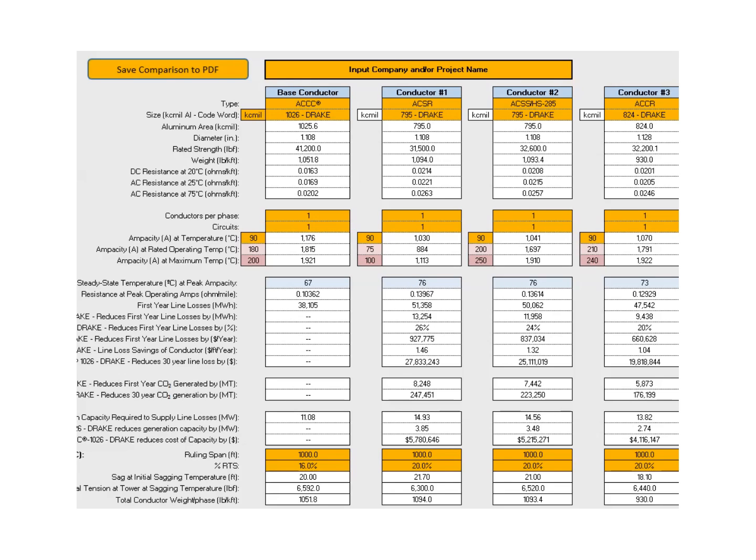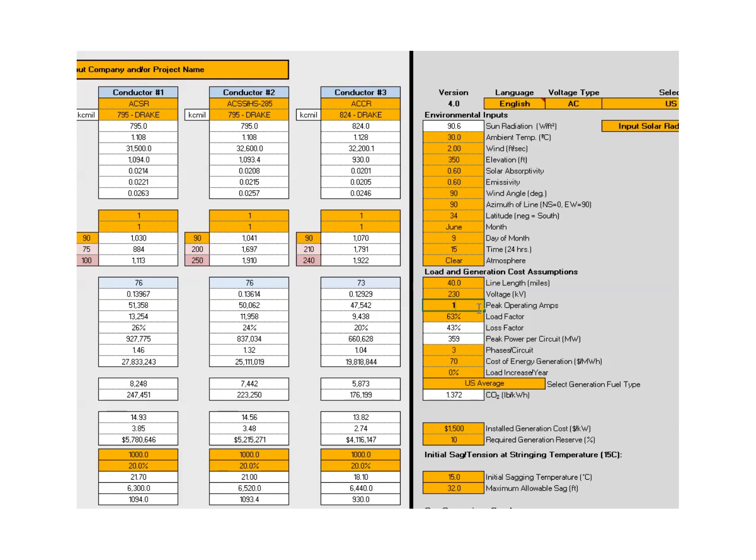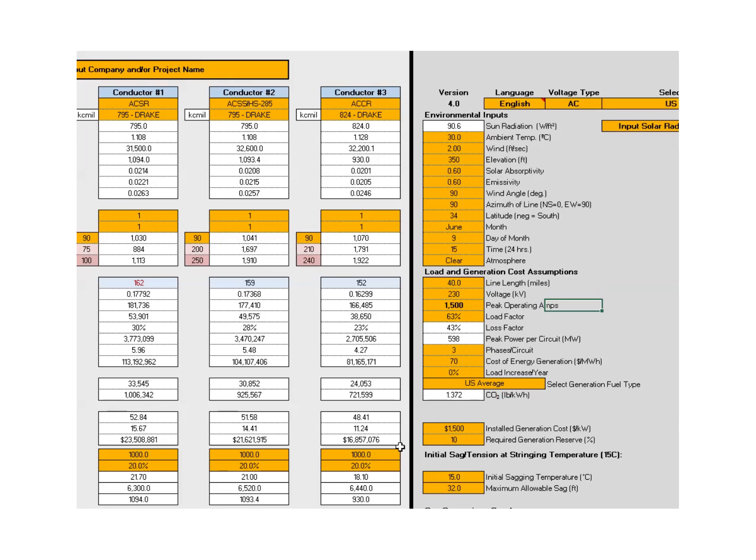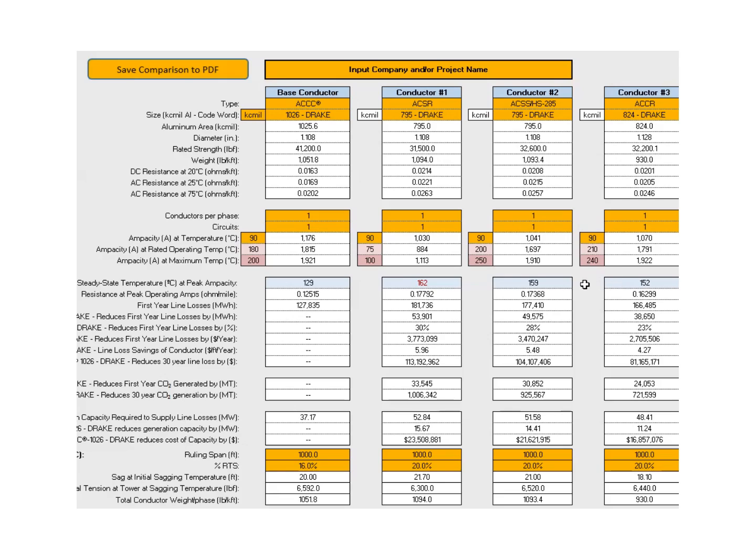When we start getting into the numbers, let's go back a moment. We started out with an assumption of peak operating amps was about 900. And when we climb back over to ACSR, we can see that the conductor temperature was about 76 degrees under these ambient assumptions at 900 amps. Well, in this case, we need to increase the amps. So we're going to go from 900, we're going to run it up to 1,500 amps. Again, that's peak amps with a load factor of 63%. When we scroll back over to the conductor comparison, we can see that at 1,500 amps with the basic assumptions, the ACCC conductor is going to run at 129 degrees C. The ACSR conductor is going to be up to, if it was still usable, up to 162 degrees C. ACSS acceptable at 159 degrees C. As with the ACCR, also 152 degrees C, which are fine because they're high temperature capable. Of course, ACSR is not generally run at that temperature.